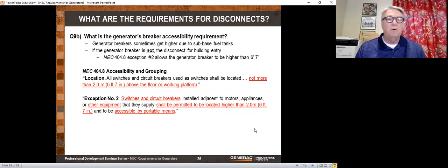So if you have a motor control center, a panel board, or a switchboard, you can't have breakers located higher than 6 foot 7 inches. Well, it turns out that on a generator, you will often have a circuit breaker, maybe it's 4 feet above the rails of the generator, and then you put it on a 3-foot tank, and now you're higher than that 6 foot 7 inches. So is that okay, or is that not okay?